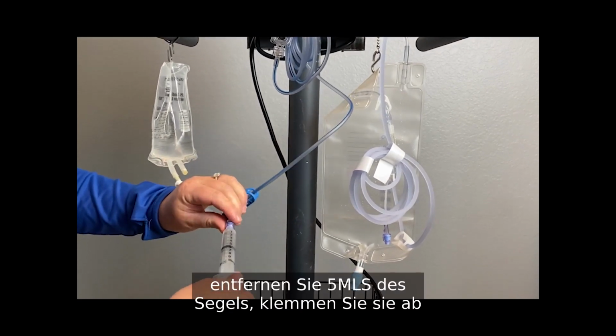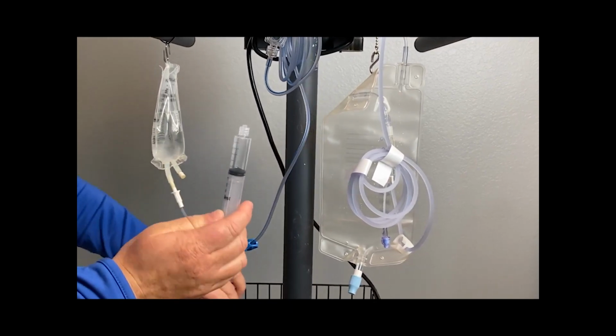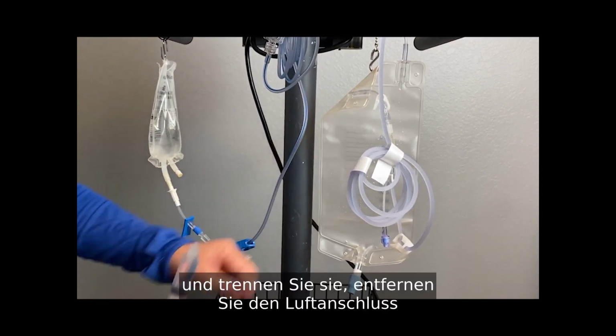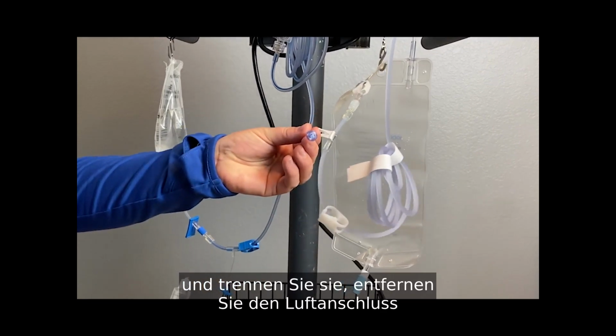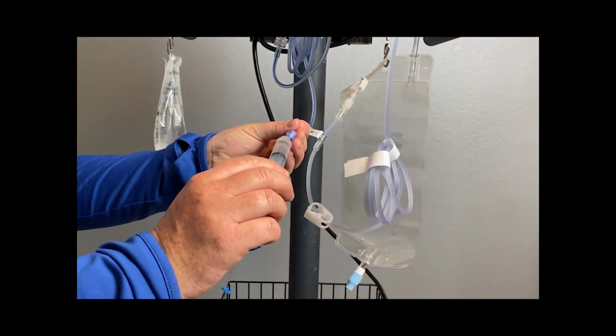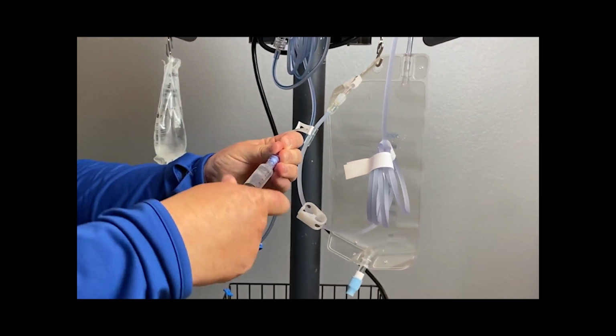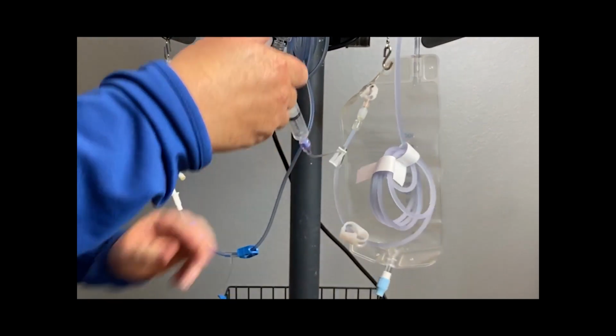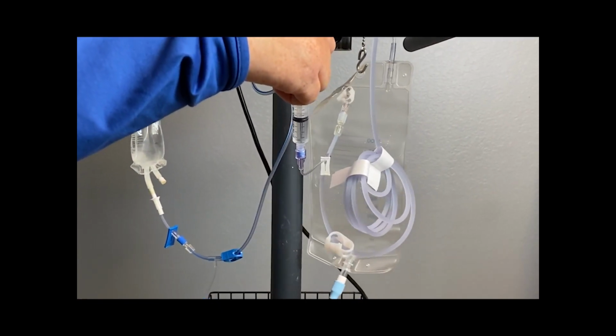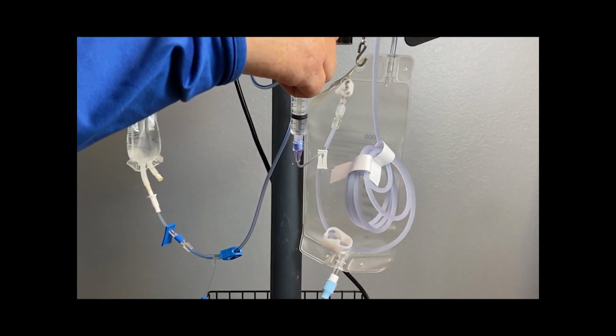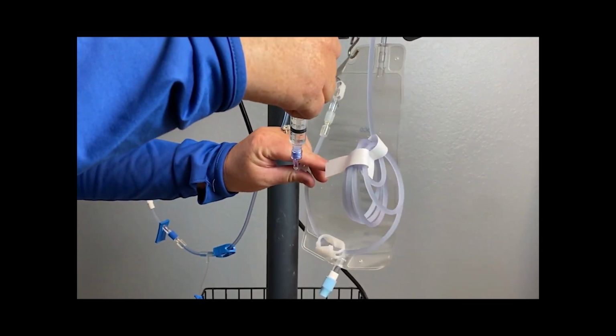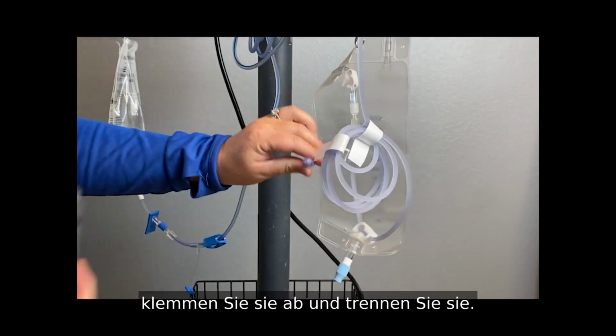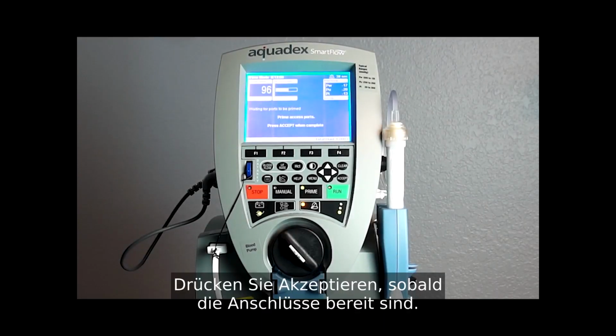Clamp and disconnect. Remove air. Connect to the infusion access port. Infuse 3 ml. Clamp and disconnect. Once access ports are primed, press accept when complete.